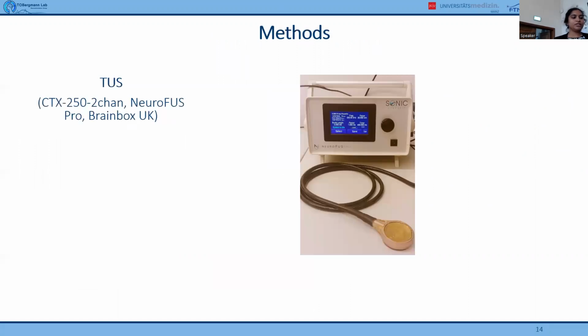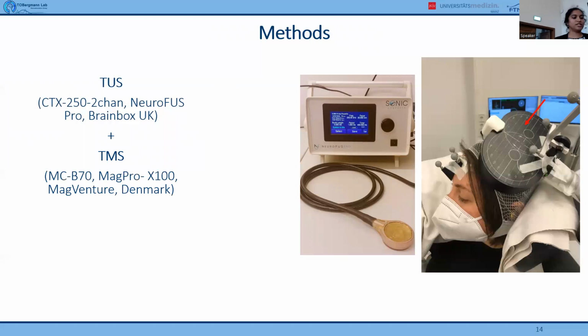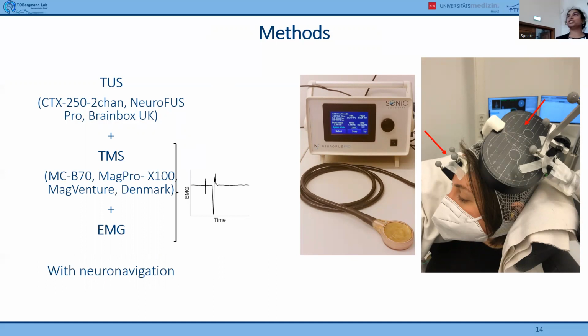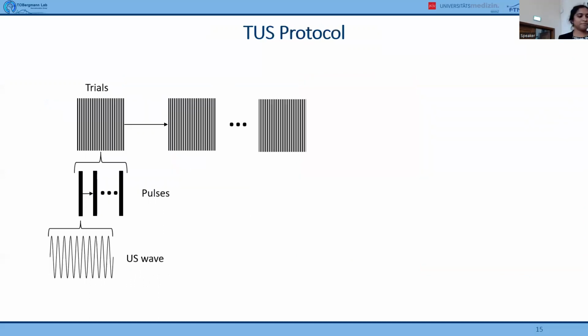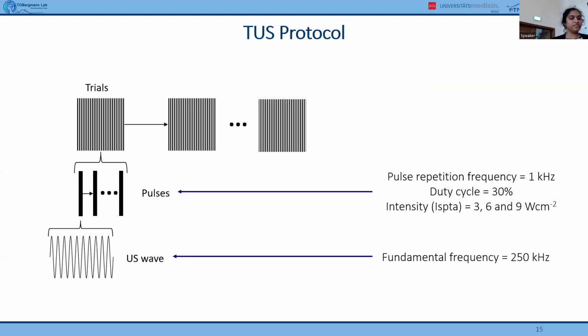For this study, we used the NeuroFUS 250 kilohertz transducer, and we paired it with TMS. So the transducer is under the TMS coil that you see in that picture, because the transducer has to be directly coupled with the head. And of course, we had EMG, so we could measure motor evoked potentials. And the whole thing was neuronavigated using that tracker that you can see on the TMS coil. The protocol that we used, 250 kilohertz, 1 kilohertz pulse repetition frequency, and a 30% duty cycle, which is what has been shown to cause suppression of MEP in previous studies.